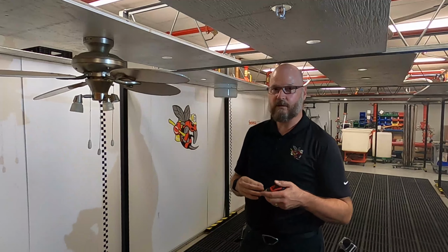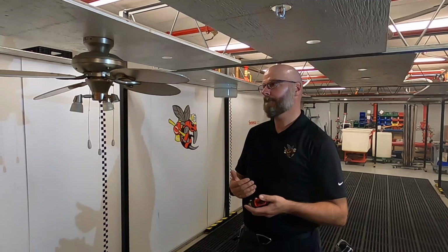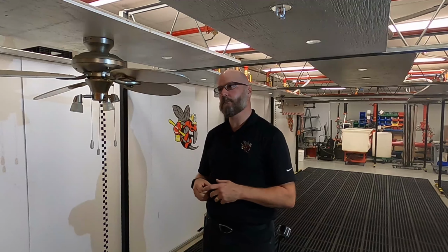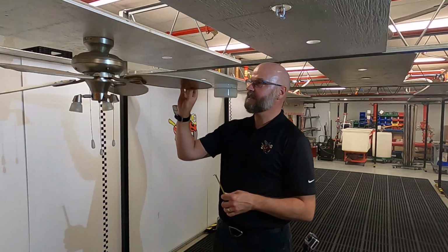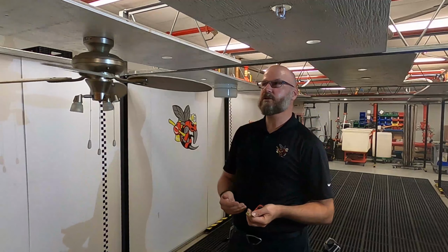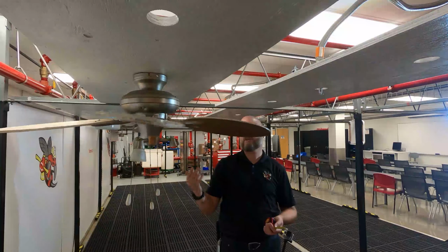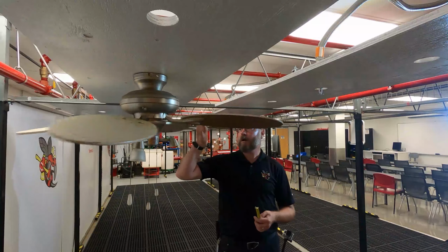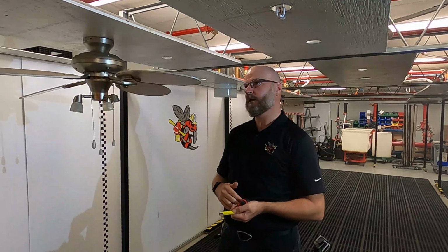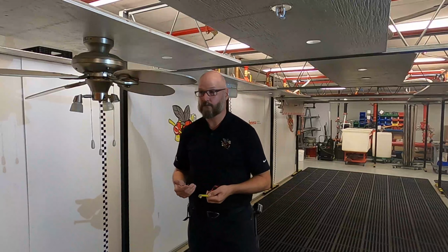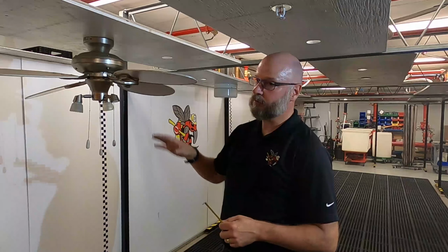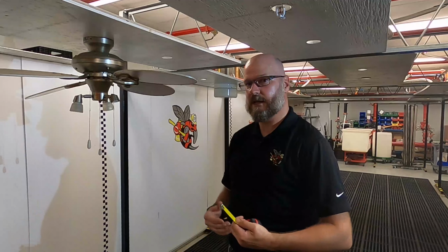But the first thing that water is going to spray into, in this case, would be the ceiling fan blade. Now, NFPA has been very thoughtful about how ceiling fans and moving obstructions may come into play. But specifically for ceiling fans, if there were to be a sprinkler discharge, how much of an obstruction would this be if it was on? Well, I'd be more concerned about it moving airflow than about it interfering with water distribution, okay?